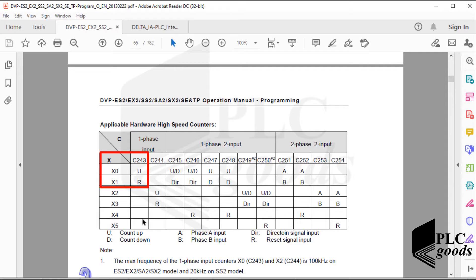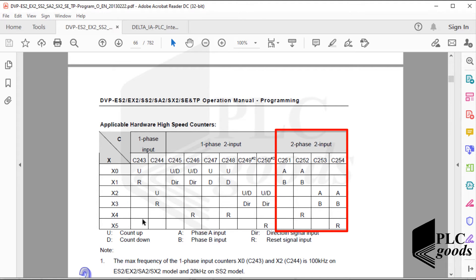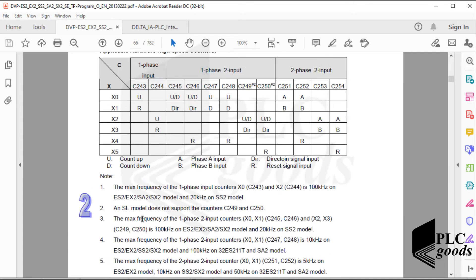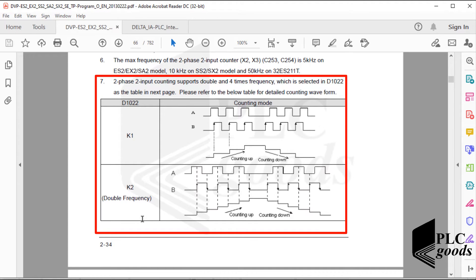For example, C243 is an up-only counter which counts signal edges at the first digital input, and its value can be reset by the second digital input. C250 counts received edge signals from the third digital input X2 and can count in both directions, which is determined by X3. This table displays how a counter's value in the last column changes based on received signals from its two digital inputs.